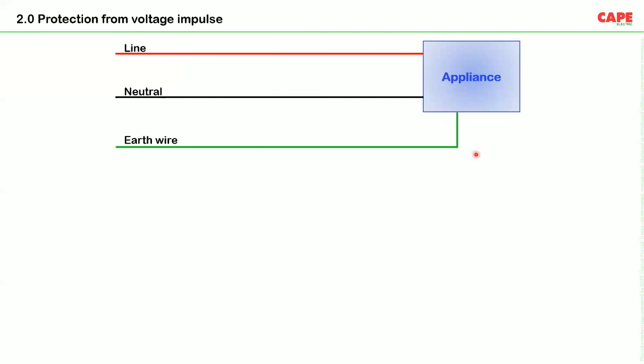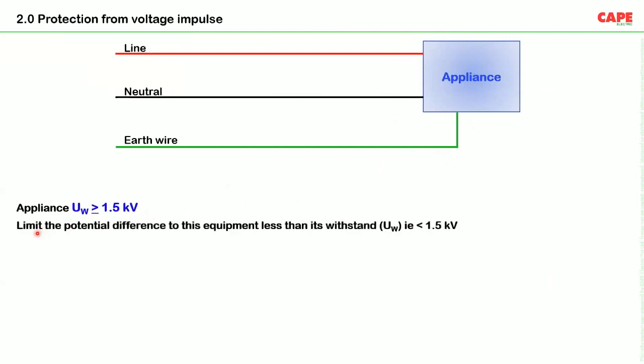We have the appliance which is connected with a line, neutral, and earth wire. Imagine our equipment, the appliance, has a withstand voltage, UW, that means the voltage impulse withstanding capacity is approximately 1.5 kV. Now, what do we do? We have to limit the potential difference to this equipment to a voltage lower than its withstand voltage. That means between the line and neutral, the appliance can withstand only up to 1.5 kV. If the voltage is more than that, of course, your equipment will fail.